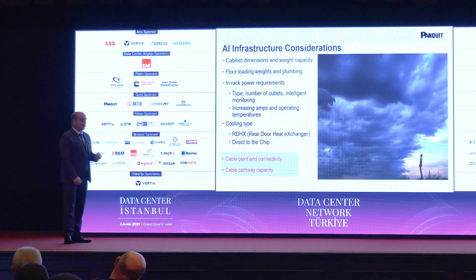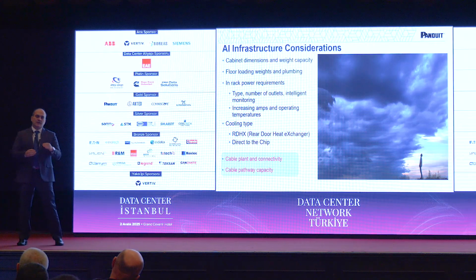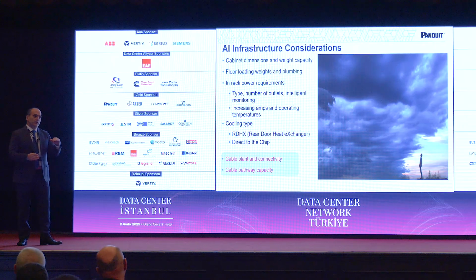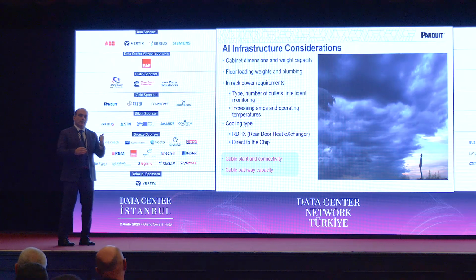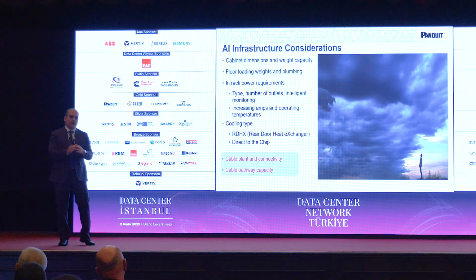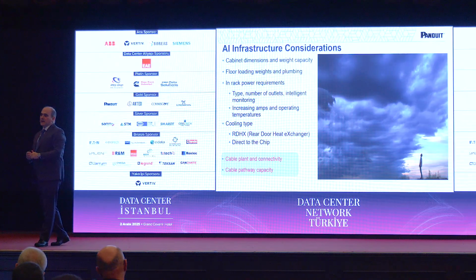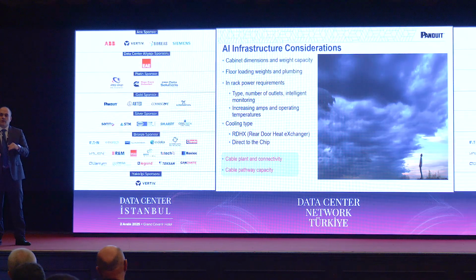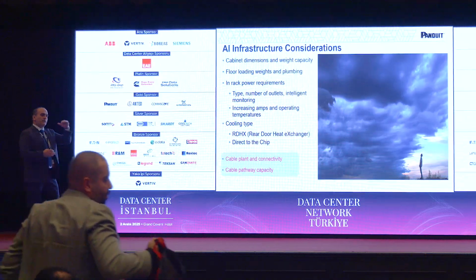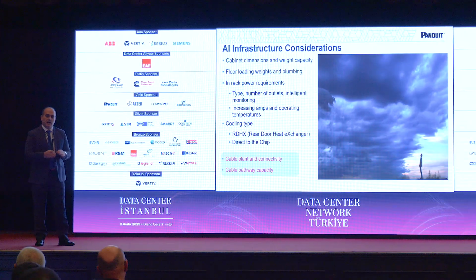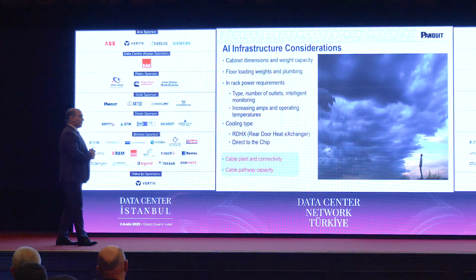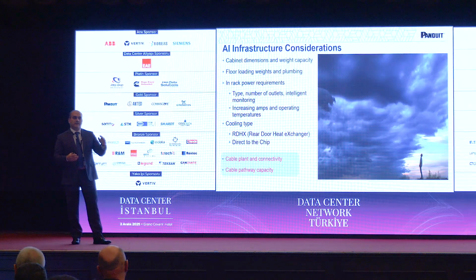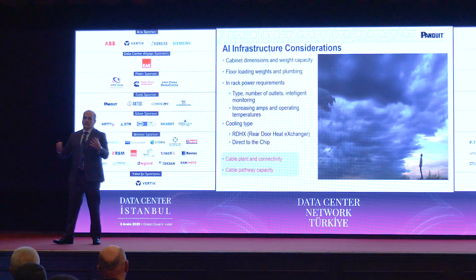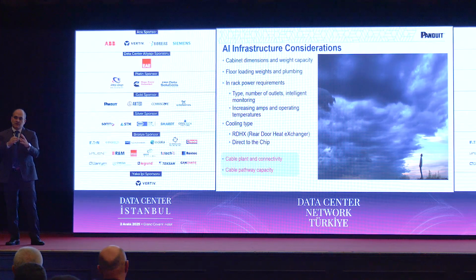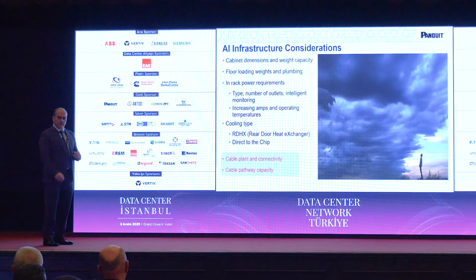And at the end, we have the connectivity we mentioned, which is an equally very important and crucial factor. As we show the amount of fiber connectivity going into such a small footprint, it requires the correct provision of pathways. We're going to see in data centers multiple layers of pathways to support this increased density and much wider bundles. And as we talk about fiber connectivity and high data rates, the way we install the fibers, bundle the cables, and manage the bend radius of all these trunk cable bundles is very important to maintain and provision the right performance of the fiber.